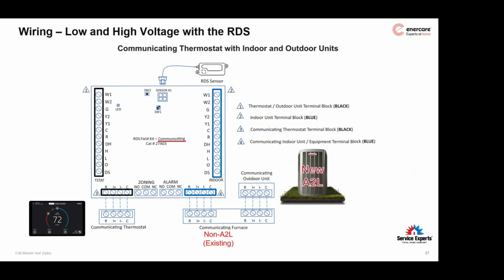We've got a couple examples here, probably the most common things you guys are going to see. This is the fully communicating external, again, I repeat, external communicating RDS field kit. It is designed to be paired with a legacy furnace. So for instance, you've got a furnace that's 5 years old, still very good. The customer, however, has to upgrade their air conditioner or heat pump, and they install some of this new A2L product. To me, this looks like the easiest way to go. Something that's communicating outdoors with the communicating equipment inside, add another 4-wire outside, pair up your new A2L system, and then have it run through this RDS board in the most simplified manner possible.